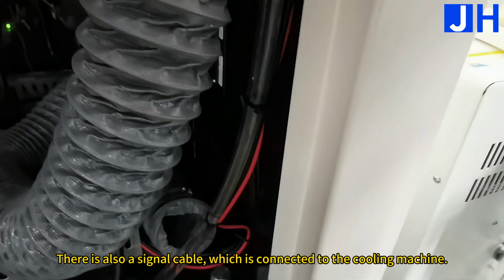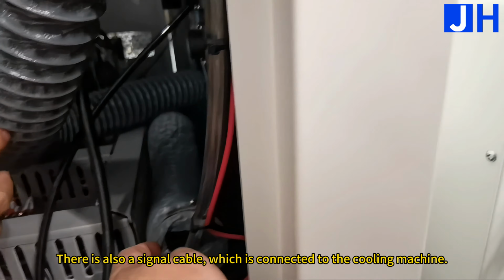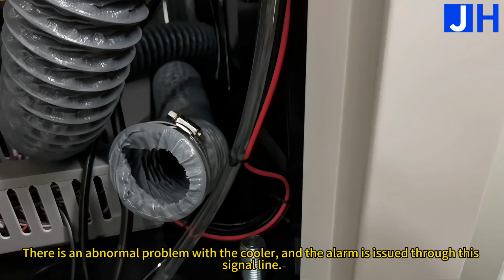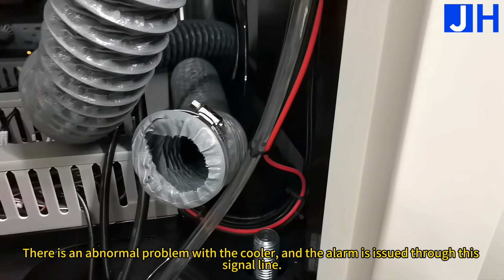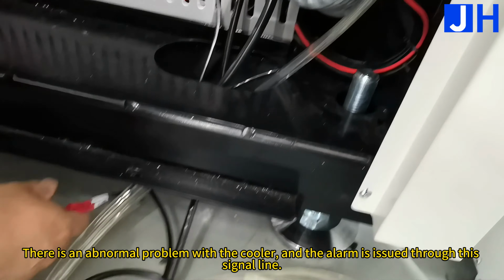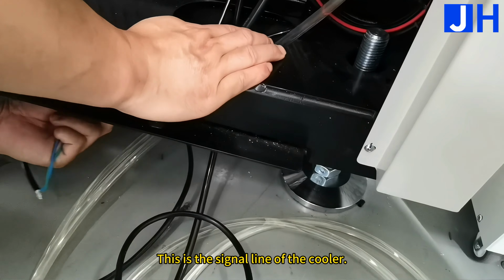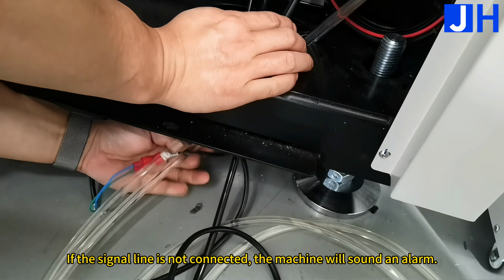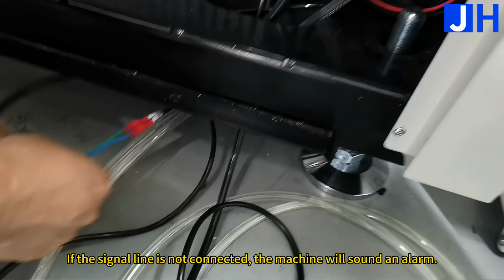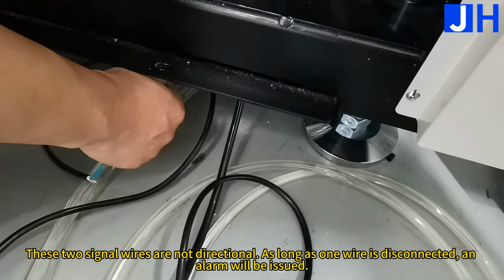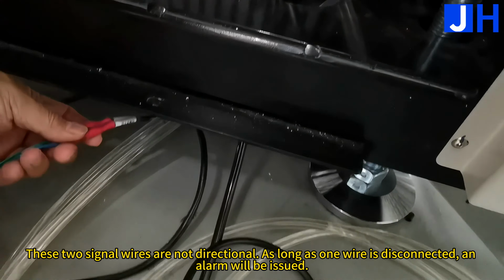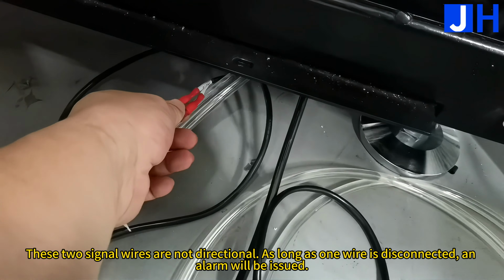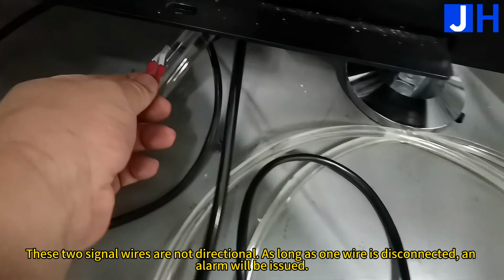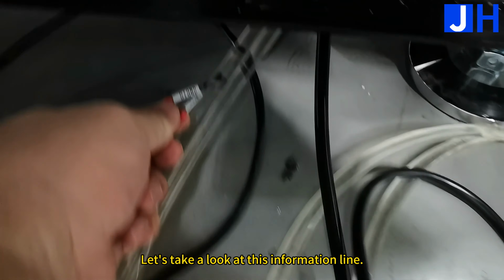There is also a signal cable, which is connected to the cooling machine. If there is an abnormal problem with the cooler, the alarm is issued through this signal line. This is the signal line of the cooler. If the signal line is not connected, the machine will sound an alarm. These two signal wires are not directional. As long as one wire is disconnected, an alarm will be issued. Let's take a look at this information line.